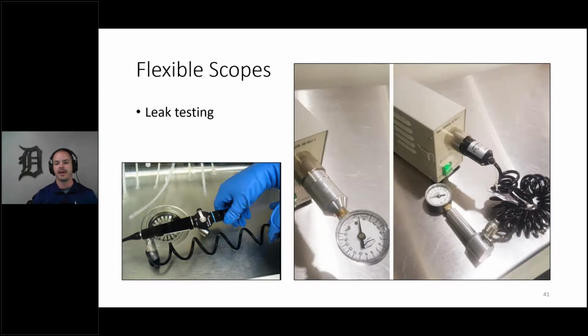I remember having an endoscope repair facility come in and audit our process, and they asked us how we check this leak tester to know if it's working. It should have a gauge on it to measure PSI, right? Our HTM partners, being as good as they were, fabricated their own PSI tester, but they embedded it right into the cord, and the manufacturer did not like that.